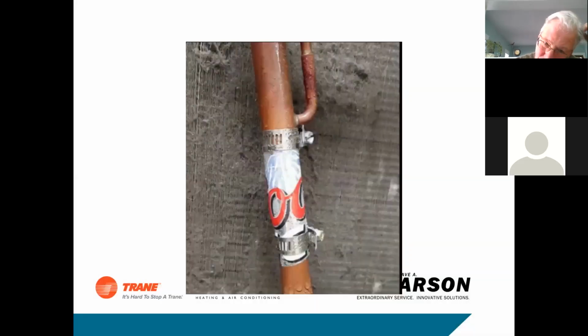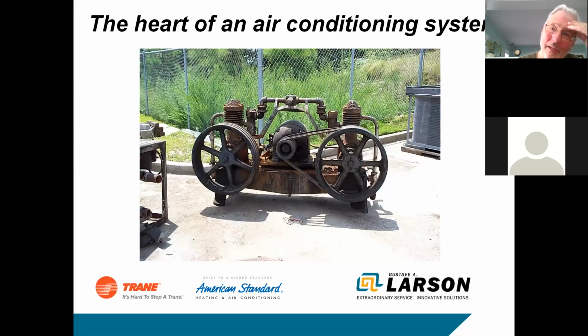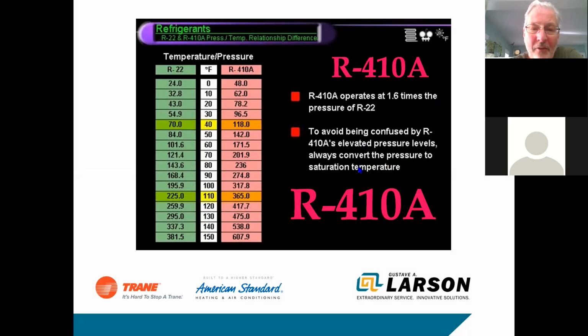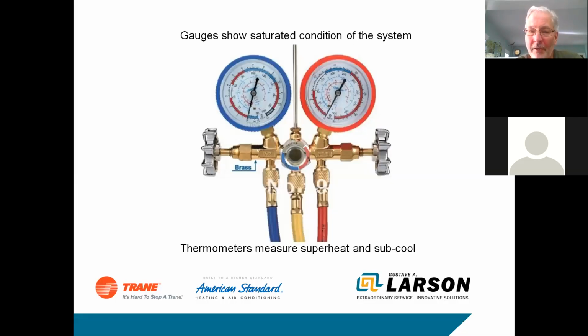Now, charging, I showed this slide earlier, but beer can cold and sweaty. Basically, the charging hasn't changed in 100 years. I mean, the compressors were a little bigger back then, but basically the refrigerant chart is the refrigerant chart. So if you put a set of gauges on a system and you see these numbers, what that's telling you is that 118 pounds of R410 is a 40-degree saturated coil, okay? 365 pounds of head pressure is 110-degree saturated coil. So that's telling you what your saturated condition is in the evaporator and in the condenser, okay? The gauges just give us that saturated condition. That's all they do for us.